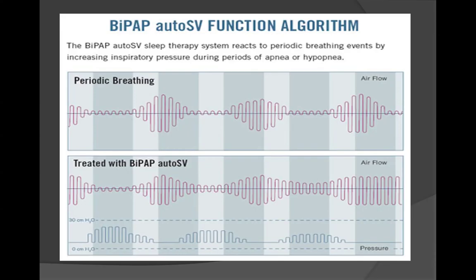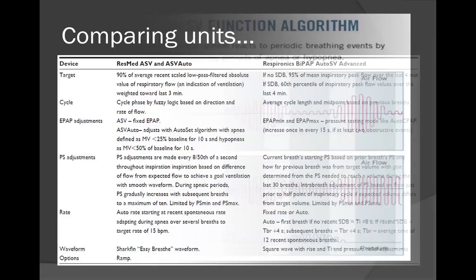So if you start the ASV while the patient is still very awake, it creates a high 90% or 95% target. So now if the patient is just starting to relax, it will already start to increase pressure because you started with the patient still on a high minute ventilation or high peak flow because they're still awake, right? We lose muscle tone and minute ventilation as soon as we fall asleep because we have less metabolic needs. All right, almost there.